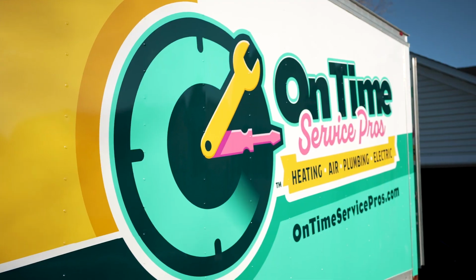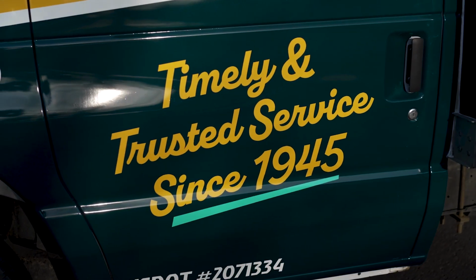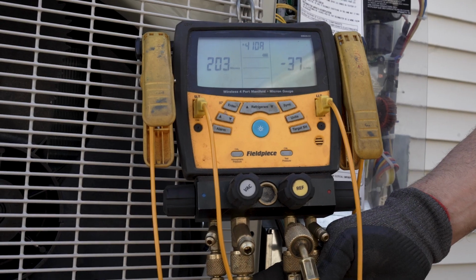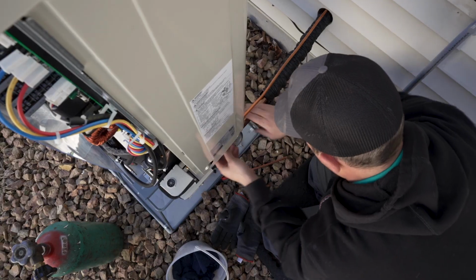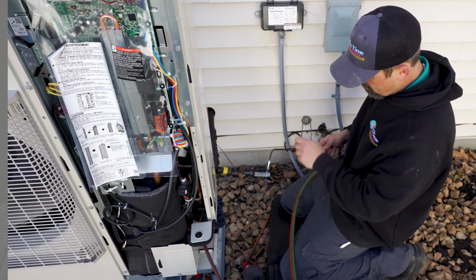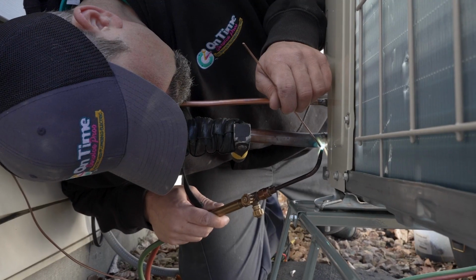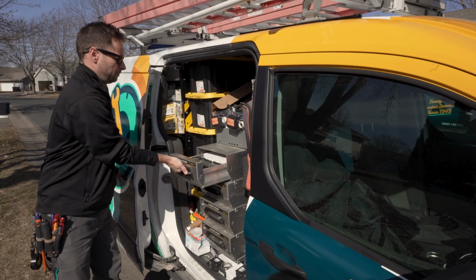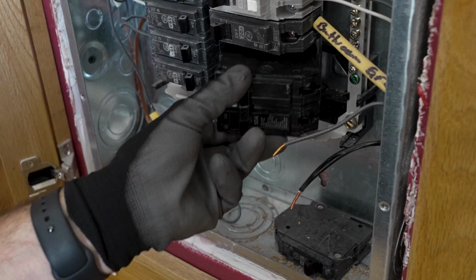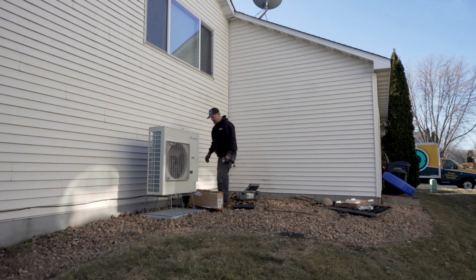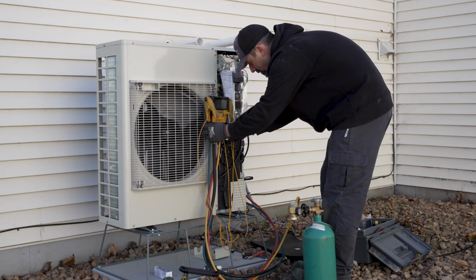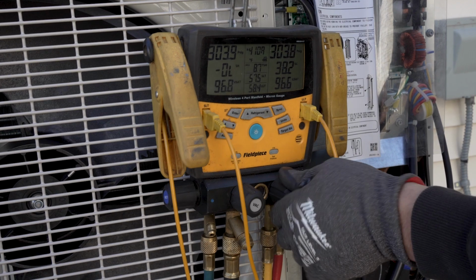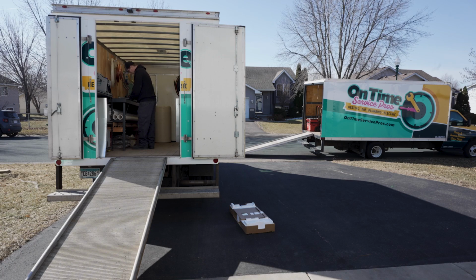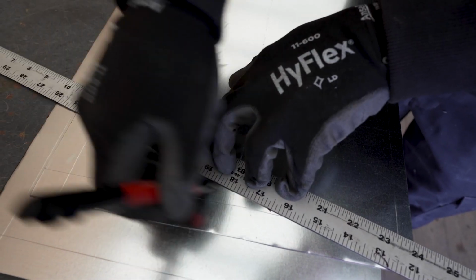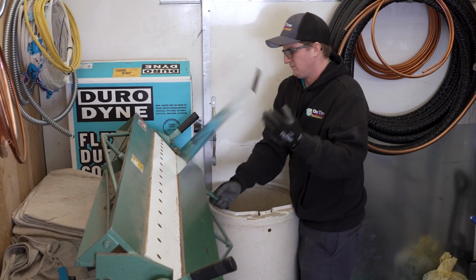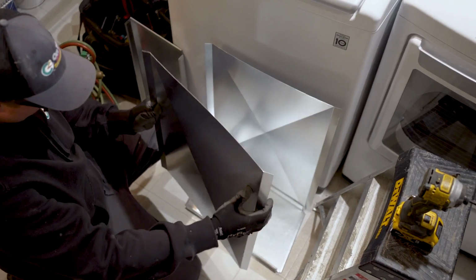What makes a great install is the attention to detail through that whole process: things like pulling a vacuum to 500 microns, is the line set the correct length and size, brazing with a trickle of nitrogen through the unit to protect the system from corrosion, are we using surge protection, is the equipment correct for the application of the house, was the Freon charge adjusted during install, and then airflow and custom ductwork. These are all things we do on every single install to ensure you get exactly what you pay for.